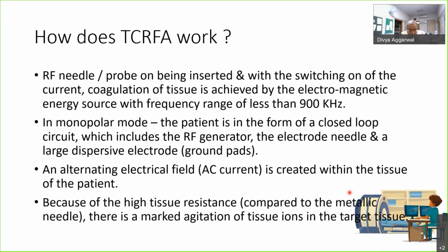There is a needle, a probe, just like cautery probes or radio frequency needles. A radio frequency needle, on being inserted and with the current of the radio frequency switched on, achieves coagulation of the tissue by the electromagnetic energy source with a frequency range of less than 900 kilohertz. RFA works in a monopolar mode, a bipolar mode, and also a hybrid mode. In a monopolar mode, the patient is in the form of a closed loop circuit.